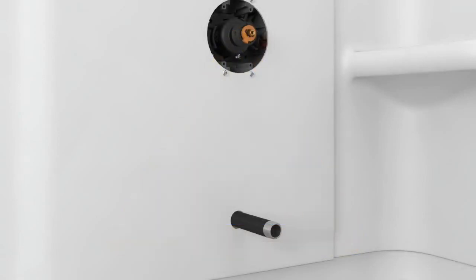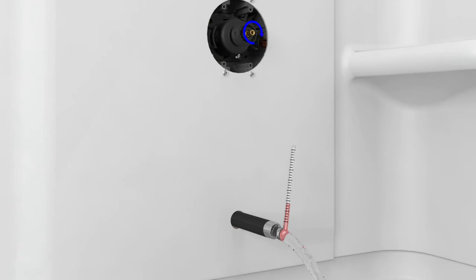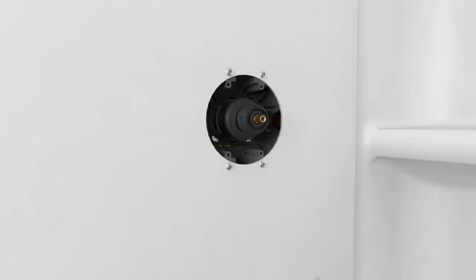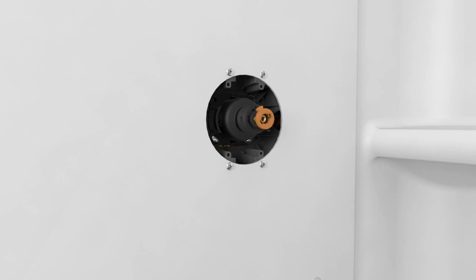To adjust the maximum temperature, remove the limit stop on the end of the valve. Open the valve and use a thermometer to measure the water temperature. When the water reaches the desired maximum temperature, replace the limit stop so it cannot turn past that point. If the limit stop does not fit flush against the tab, flip the stop over for a better fit.